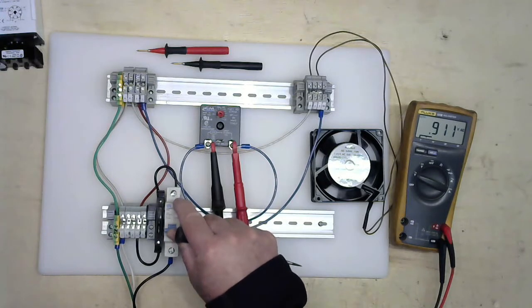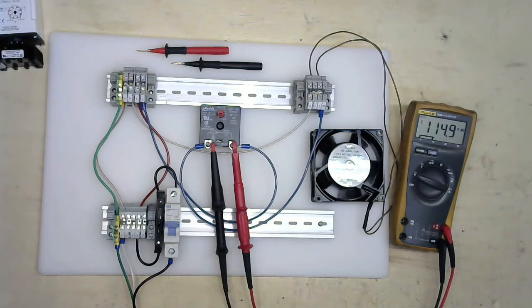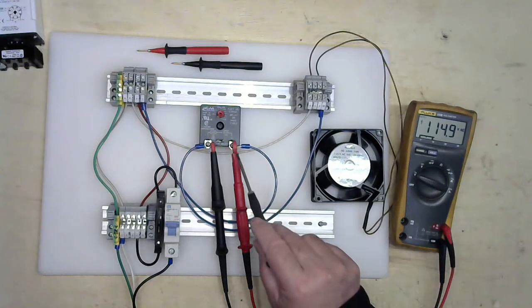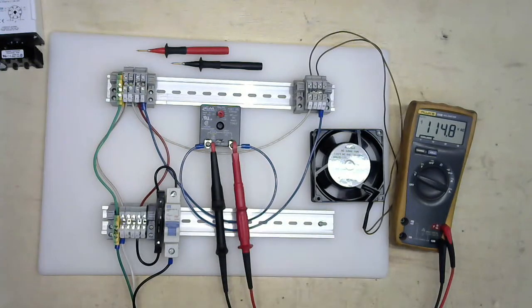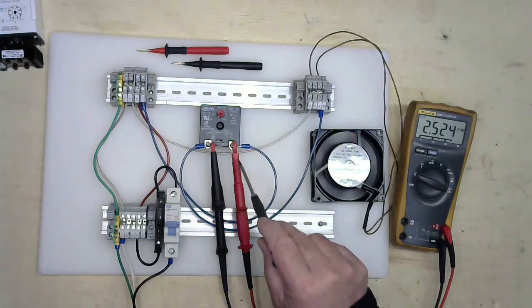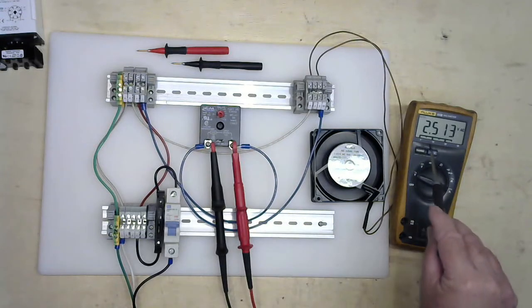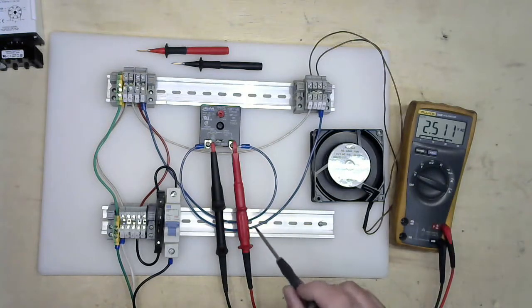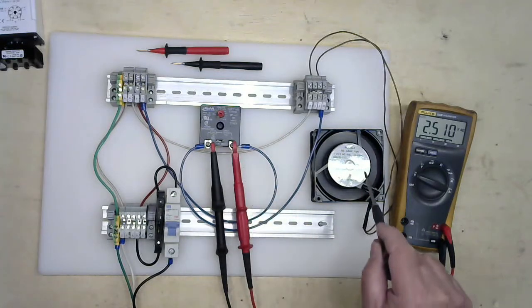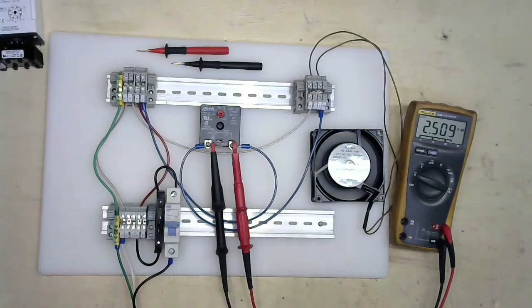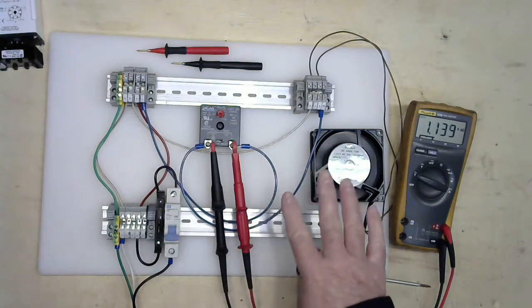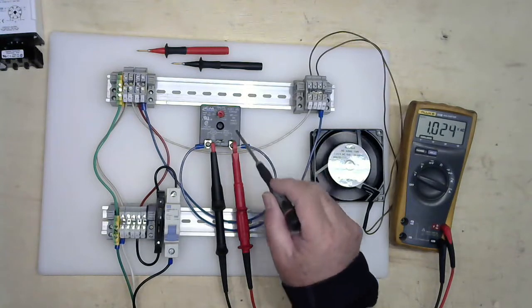Once I apply voltage, I have nominal voltage here. My timer is timing out and my motor has not started. Now my motor has started. My contacts are showing 0 volts or 2.5, some ghost voltage leaking through. It's showing me now that my contacts here are closed. My fan is now receiving the applied power. If I turn this back off, my load shuts down. So this is a delay on make timer.